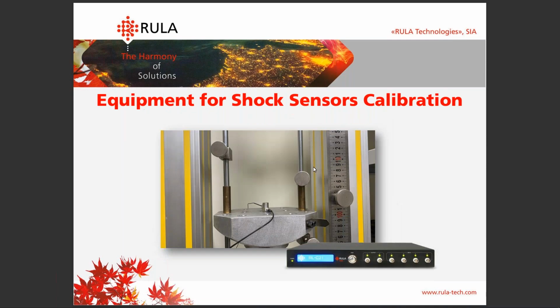Now for shock sensor calibration, essentially you're going to need the controller and you will need a shock machine. There is a whole range of brands and kinds, so we're just featuring one way it could look. And of course, you're going to need a reference sensor and your sensor under check.